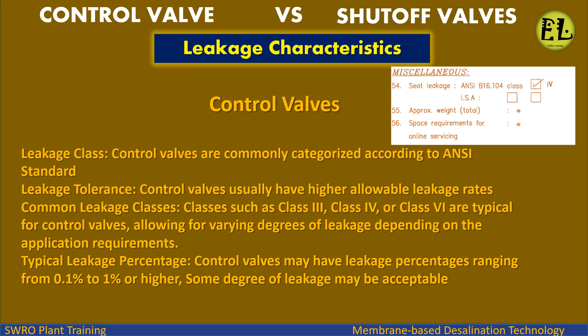Regarding leakage characteristics, control valves are commonly categorized according to ANSI standards. Control valves usually have higher allowable leakage rates, with common leakage classes such as Class 3, Class 4, or Class 6 being typical, allowing for varying degrees of leakage depending on application requirements. Control valves may have leakage percentages ranging from 0.1% to 1% or higher.